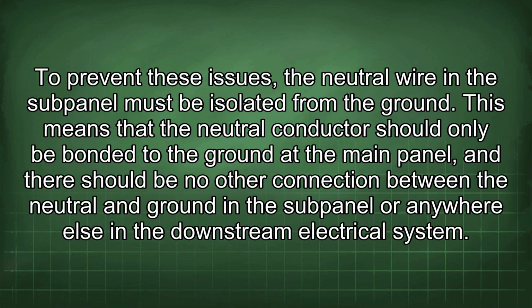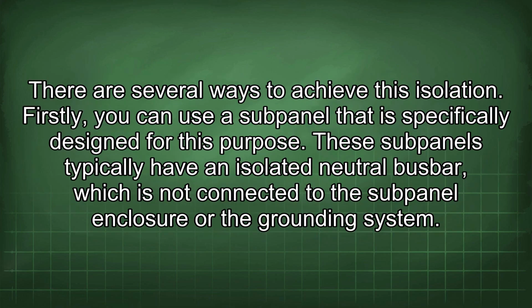To prevent these issues, the neutral wire in the subpanel must be isolated from the ground. This means that the neutral conductor should only be bonded to the ground at the main panel, and there should be no other connection between the neutral and ground in the subpanel or anywhere else in the downstream electrical system. There are several ways to achieve this isolation. Firstly, you can use a subpanel that is specifically designed for this purpose.